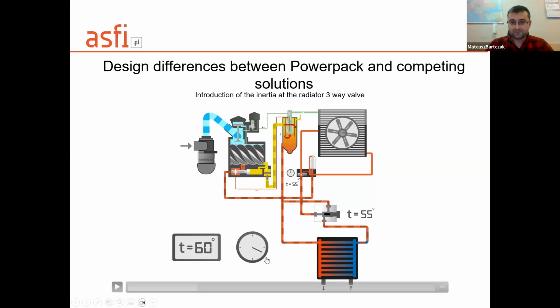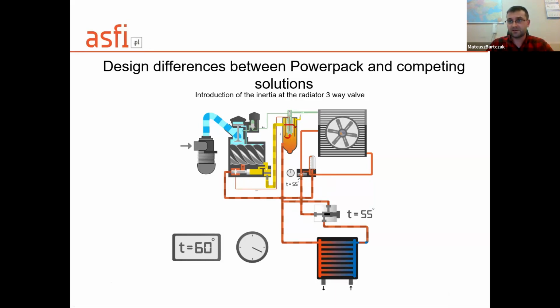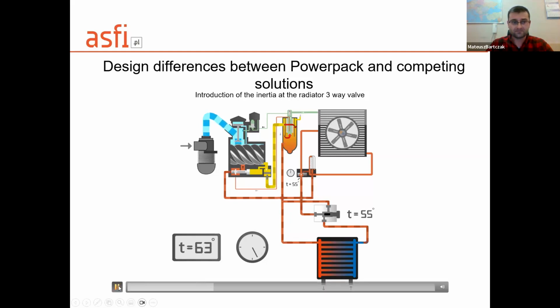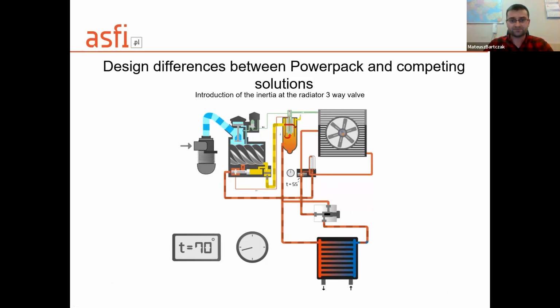Now it's 60. But the valve near the radiator doesn't see it. Why? Because this warmer oil from the separator is mixing, through this valve, with the overcooled oil from the heat exchanger. And I will stop now again. So as you see, in the separator you have 70 degrees, but this valve still doesn't see that, because we still have this overcooled oil from the previous situation.